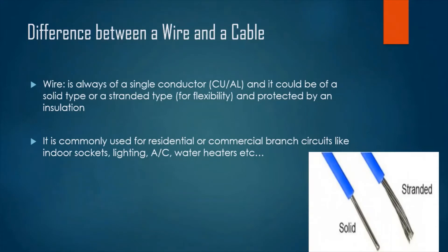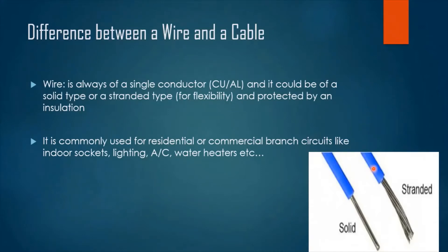First, let's have an idea about the difference between a wire and a cable. A wire is always of a single conductor, which could be copper or aluminum, and it could be of a solid type or stranded type, protected by an insulation layer. The wire has two layers: the conductor, which could be solid or stranded for more flexibility, and the insulation layer, which is always PVC. We mainly use wire for connecting branch circuits that do not consume high loads, like sockets, lights, air conditioners, water heaters, and other low-load appliances.